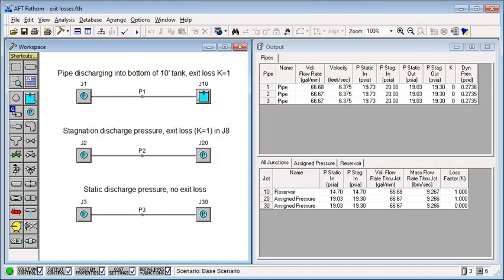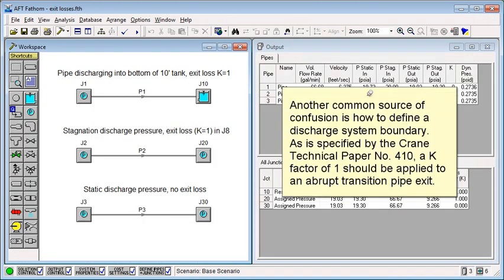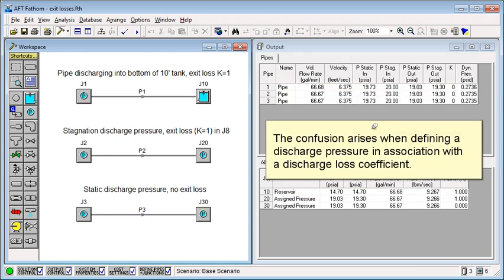Another common source of confusion is how to define a discharge system boundary. As is specified by Crane Technical Paper 410, a K-factor of 1 should be applied to an abrupt transition pipe exit. The confusion arises when defining a discharge pressure in association with a discharge loss coefficient.